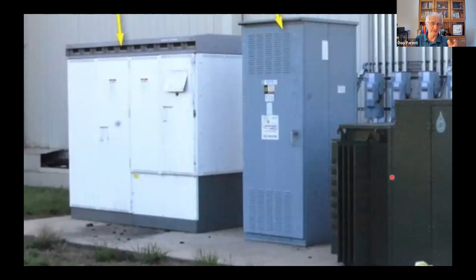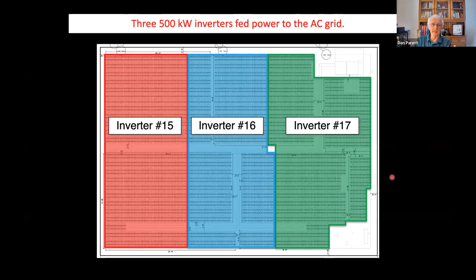And so the next step was to look at the inverter. The inverter is approximately the size of 2 refrigerators. And the inverter tracks current and voltage and power production, I think like every minute. And there's a small SD card in the device, and it writes to a file. It records all that data in an Excel readable format, turns out. So there's, as I said, 3 inverters. And inverter 16 is the inverter that essentially surrounds the area where the fire actually started, the origin of the fire. So what we decided to look for is, what are the characteristics of these 3 inverters? How are they performing? And is there anything novel or unique about inverter 16 that might indicate that there's something going on on the roof?